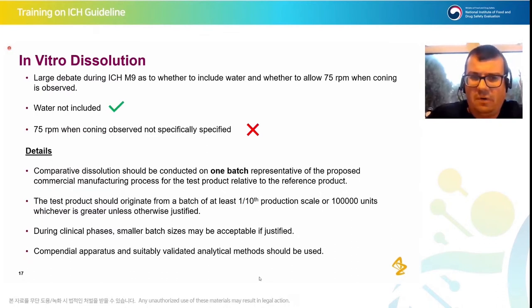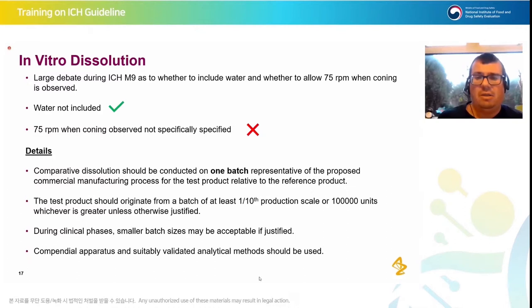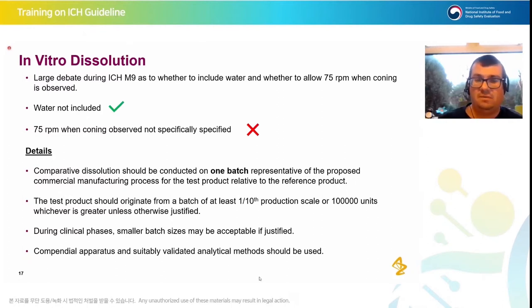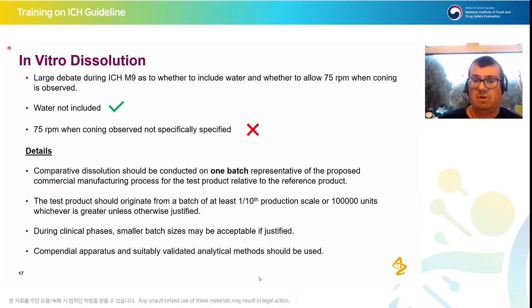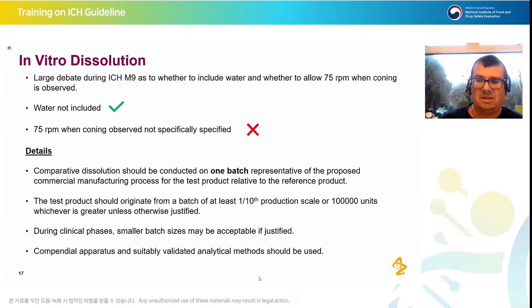Now covering the in vitro dissolution part of the drug product assessment. There were two major debates during ICH M9: whether to include water as a medium, and whether to allow 75 rpm when coning is observed. Water wasn't included — in my personal opinion it doesn't add much and is variable across laboratories. The 75 rpm option wasn't explicitly specified — we'll come back to that. For comparative dissolution, you need one batch representative of the proposed commercial manufacturing process for the test product relative to the reference product.